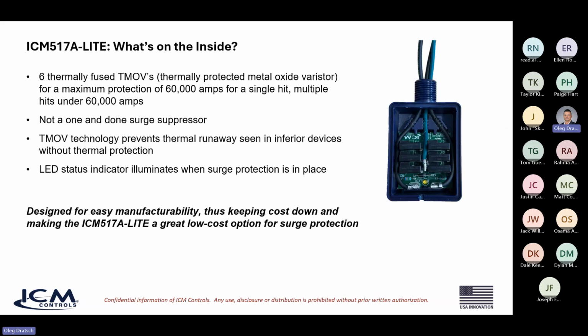On the inside, I mentioned it earlier, there are 6 thermal metal oxide varistors. One hit, it can take up to 60,000 amps. Now it can survive a number of hits under 60,000 amps. Essentially, these TMOVs, and you see them right here, are wired in parallel on one side and the next. Each one would provide protection until it was no longer able to do that, then it would move on to the next one, then the next one. So it's not a one and done surge suppressor. It will withstand multiple strikes as long as they are under 60,000 amps. The TMOV technology can help prevent thermal runaway that we've seen in some of the competitive devices on the market. Like I mentioned before, you see the green LED here that will illuminate when your surge protection is in place.